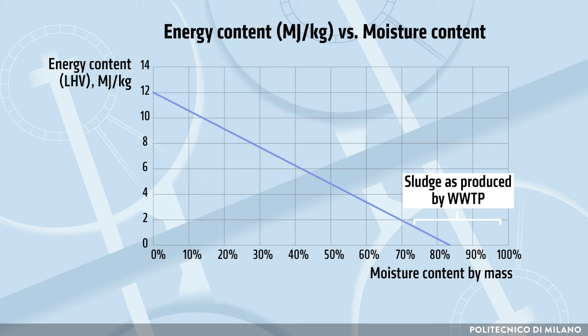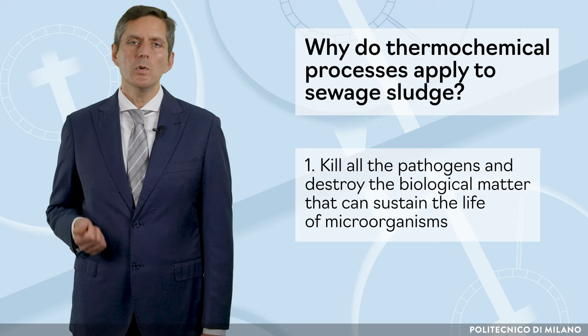Therefore, why do thermochemical processes apply to sewage sludge? First, because these processes kill all the pathogens and in most cases destroy most, if not all, the biological matter that can sustain the life of microorganisms. Moreover, the higher the temperature, the lower the number and the complexity of the chemical species produced by the process. Having to deal with a limited number of chemical species is a very relevant advantage in preventing pollution. Second, they reduce considerably the amount of solid residue to be handled. Third, they concentrate some valuable elements like phosphorus into this reduced amount of solid residue, opening the possibility for recovery processes.